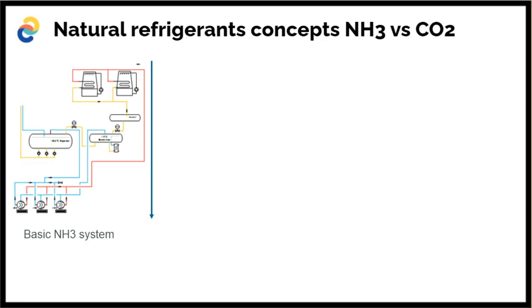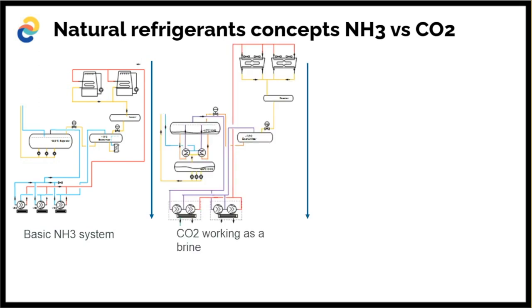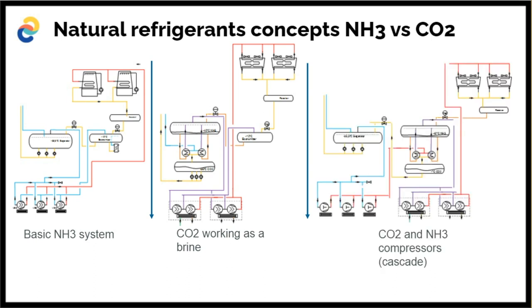And that's here what we use: a very safe and robust system, CO2 working as an evaporating brine. It gets a little bit more complicated because you have some extra condensers and cascade condensers here. It's a bit more expensive. But here you will have only ammonia compressors in the machine room, with underneath a pump system that pumps CO2 to the coolers, and it returns back again. And the last one we use a lot is the CO2 and NH3 compressors, a so-called cascade system.